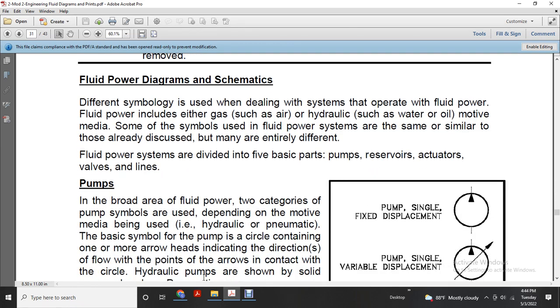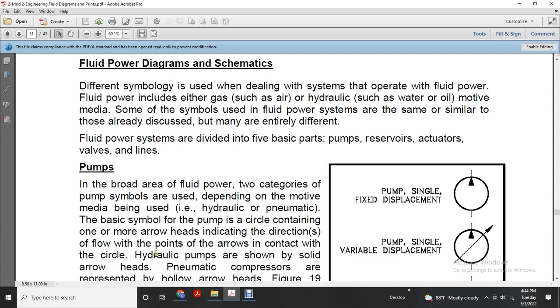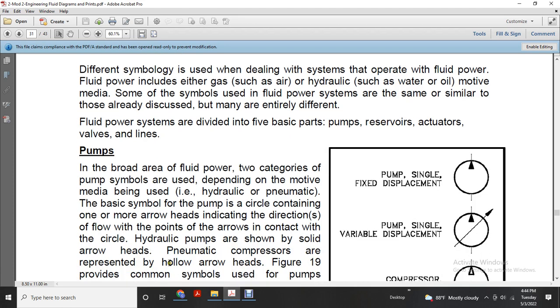Pumps are a broad area, with two categories depending on the motive media, being hydraulic or pneumatic. The basic symbol of the pump is a circle containing one or more arrowheads indicating the direction of flow. Hydraulic pumps are shown with solid arrowheads. Pneumatic compressors are represented with hollow arrowheads.